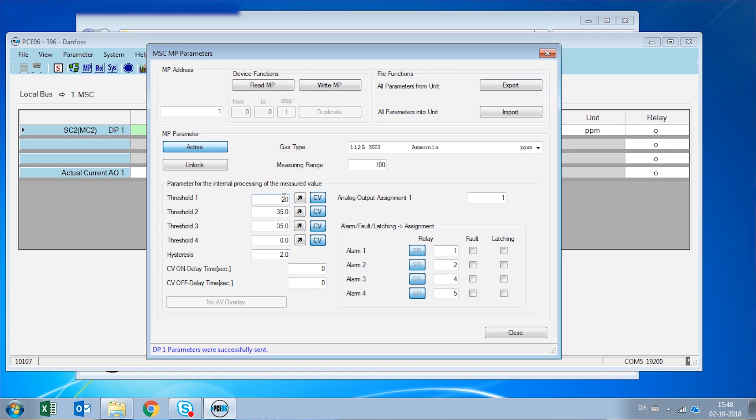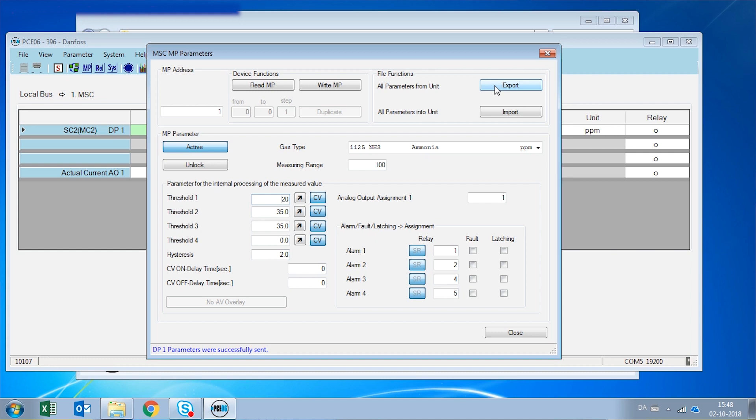Another function of this menu is that we can export all these parameters into a CSV file that can be then sent by mail to a different location for other digital gas detector to be set up exactly the same way. And by the same means we can import parameters from another digital gas detector to have a duplicate of that one. So we're going to move to the next menu.